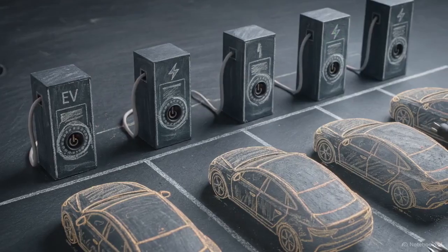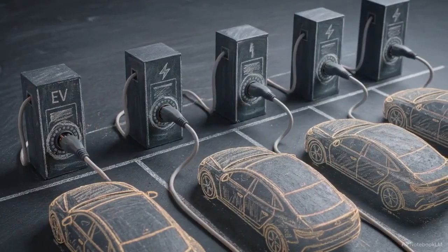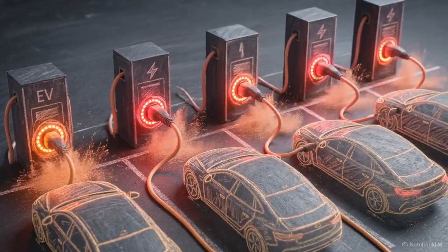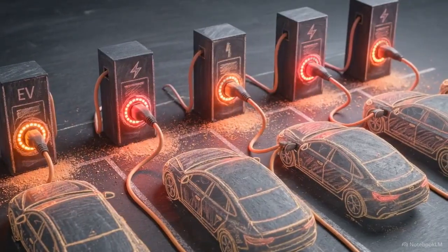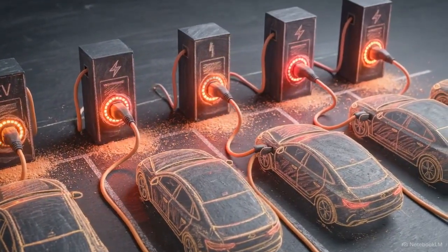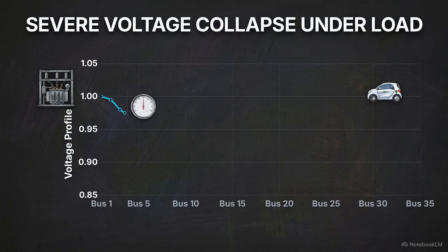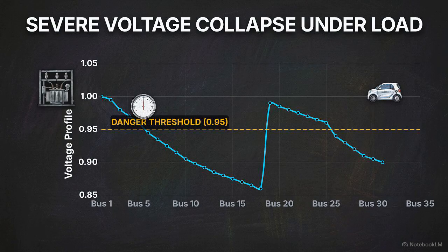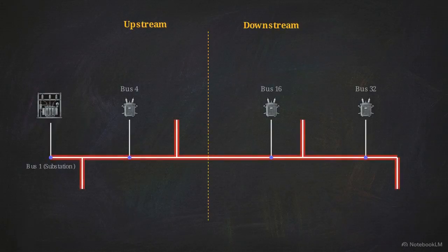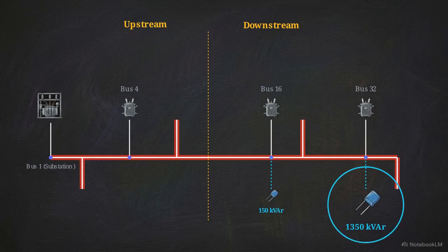Finally, the ultimate stress test. The 125% EV peak scenario simulates the massive power surge of evening EV fast-charging clusters. The baseline conditions here are severe. The initial active power loss reaches nearly 330 kilowatts, pulling the midsection buses into dangerously deep voltage drops. The algorithm counters with a radical adjustment, splitting the placements between buses 4, 16, and 32. The bulk of the power, 1350 kVAR, is stationed to guard the highly vulnerable tail at bus 32.